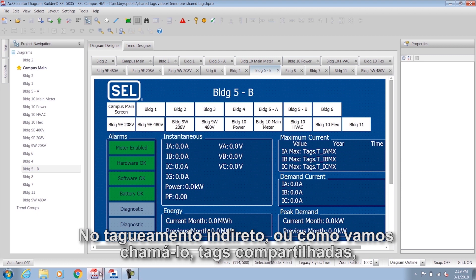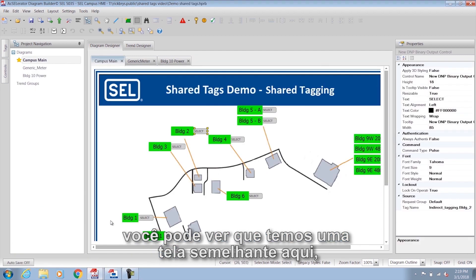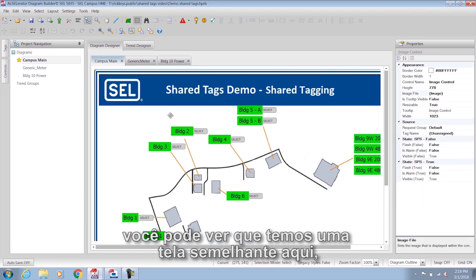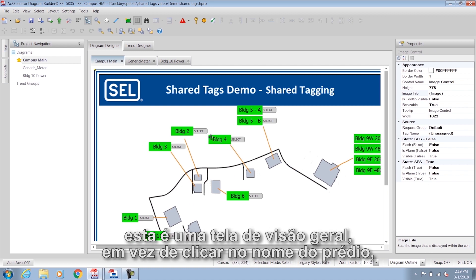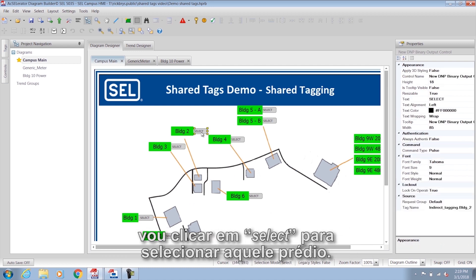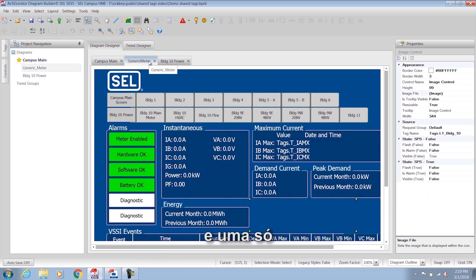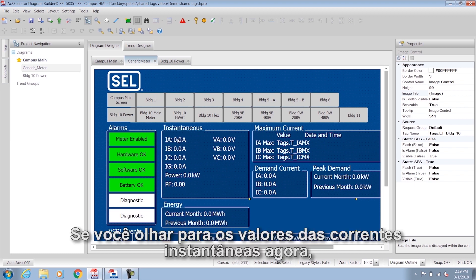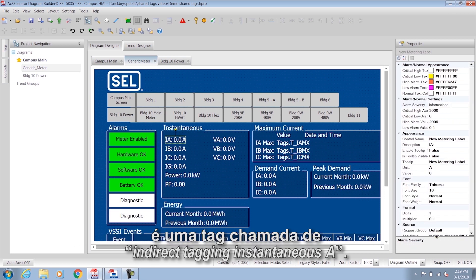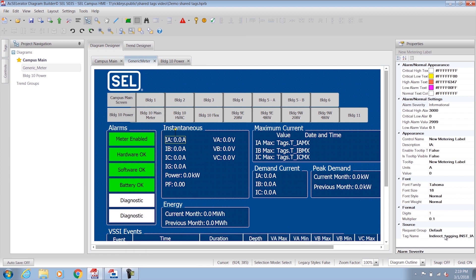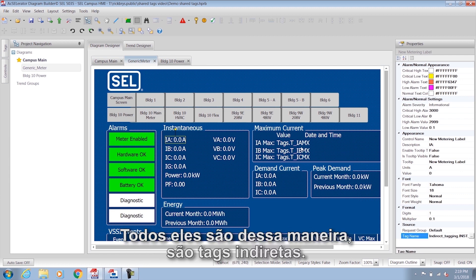In indirect tagging, or shared tags, you can see we have a similar screen — this is an overview screen. Instead of clicking on the building name, I click 'select' to select that building. If you look at the tabs, we only have one screen — just one — for all of those buildings. The values for instantaneous current are now a tag called 'indirect tagging instantaneous A,' and all of them are indirect tags.